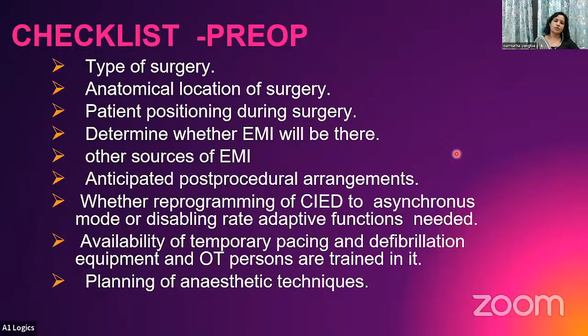Okay, is reprogramming required in all devices? It is a big no. First, surgical procedures where there is a high incidence of electromagnetic interference. Second, if the patient is pacemaker dependent. Third, if the surgery is going to interfere with the site of the pacemaker implantation. Fourth, the patient is having an ICD, that is, rate adaptive features. Then you have to change the pacemaker to the asynchronous mode. Otherwise, there is no need to reprogram.